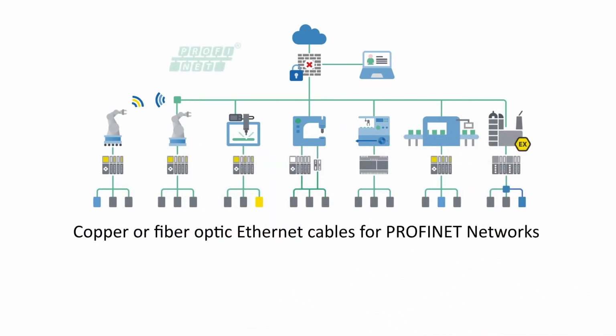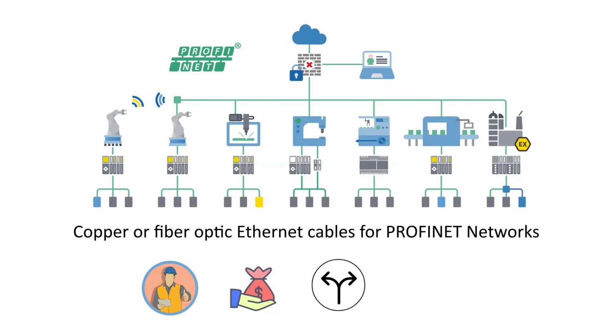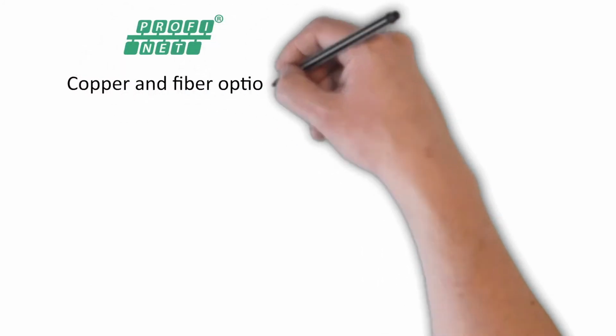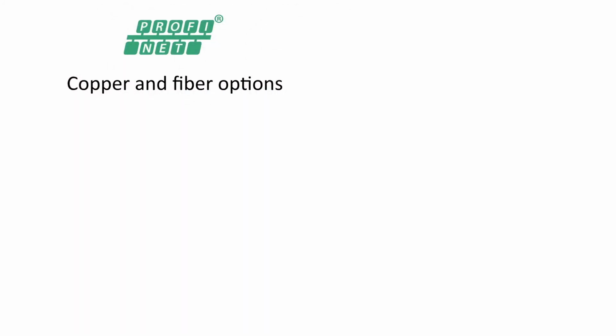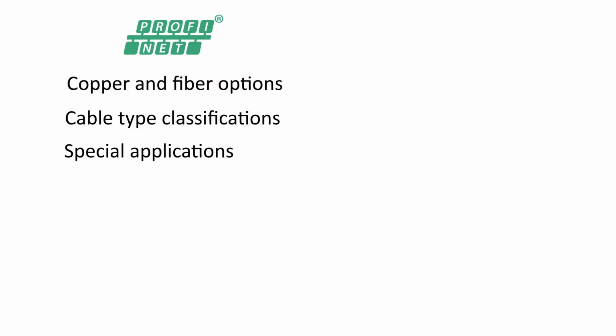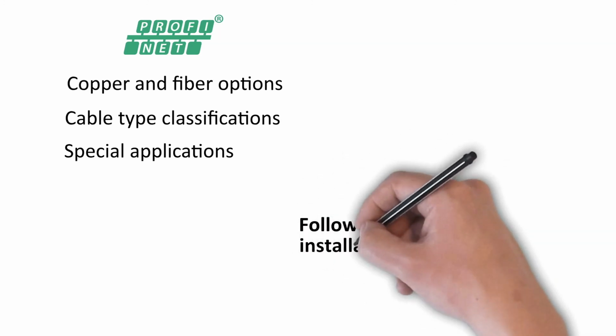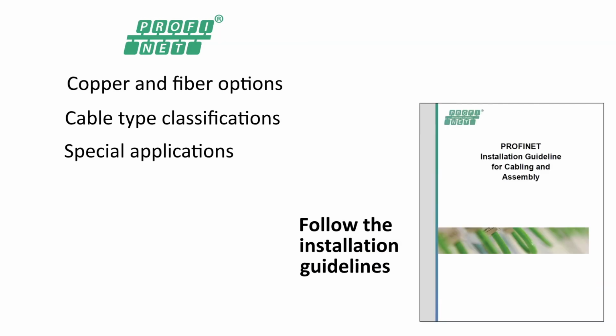Utilizing Ethernet cables is a huge benefit as they are extremely common, affordable, and versatile. There are many cable manufacturers offering competitive products. You are always able to find the right cable for each Profinet connection. Copper and fiber cables have type classifications to indicate what degree of movement they are built to withstand, and manufacturers also offer cables for special applications. Finally, when commissioning copper or fiber cables, always remember to follow proper installation guidelines available for free from us at PI.